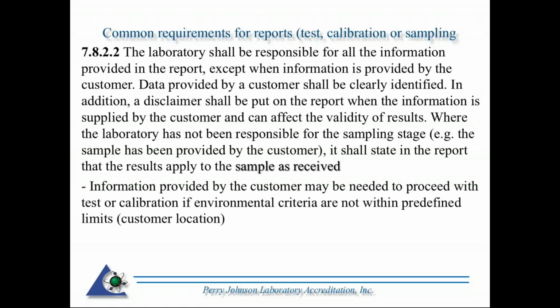Now that second part about deviations, probably the most likely scenario where that may come into play, and it is spelled out earlier in the standard, especially under the environmental section, is for those folks that are going off-site and doing calibration. So perhaps you have predefined limits that your calibration procedure specifies it needs to be performed at, let's say between 20 degrees C plus or minus 3 degrees C. Hence, if you go into a customer facility, it may not be as tightly controlled as your lab. So you're actually going to be deviating from the procedure there.